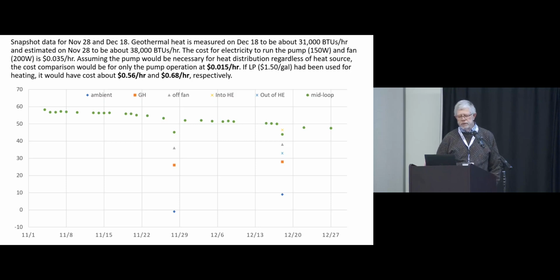The flow rate I don't show here, but it was about 4.8 gallons per minute, so you can calculate that's about 31,000 BTUs per hour. I didn't have the temperature ports in on the 28th of November, but just projecting from the other temperatures, I'm guessing that was about 38,000 BTUs per hour.